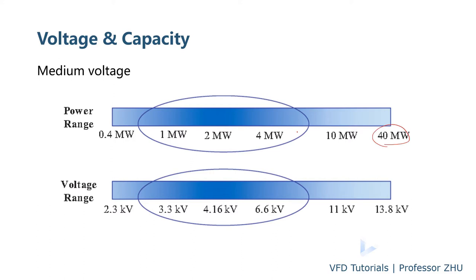This is generally speaking, but sometimes you have big motors which are driven by VFD. Like my company Nanko, we built the largest medium voltage drive in the world for a 120 megawatt motor. This is an 18 kV dual winding motor for a test bench. For the voltage, the typical voltage is from 2.3 kV to 10 kV. The majority is from 3 kV to 10 kV.